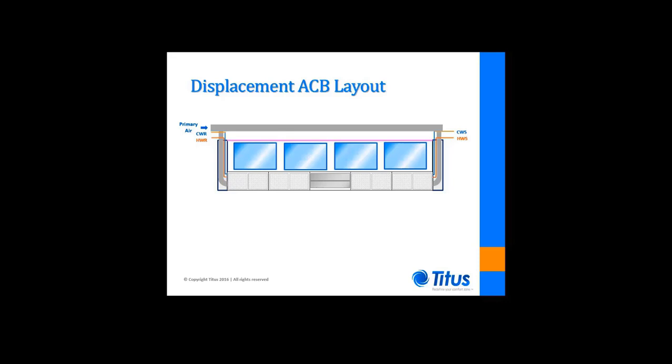The individual TAO heat transfer coils are fed in parallel, and the piping is run behind the units and against the wall. Primary air is supplied to multiple TAO units in series. A single duct connection should be limited to feeding no more than 3 units due to noise and pressure limitations. So often this involves air supply connections on both sides of the classroom.